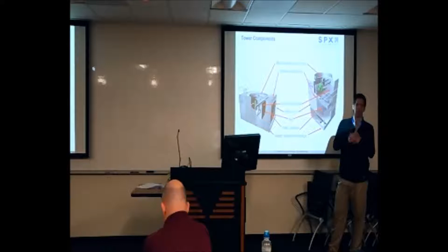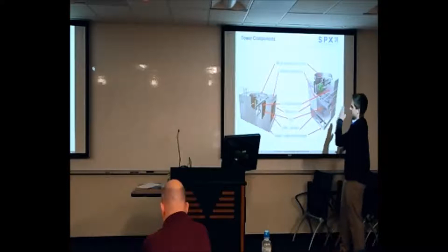We also have, integral to the fill, louvers, which are the first point of contact for the air. The purpose of the louvers is to keep the water inside the tower. Without louvers, the water would just fall out of the fill. It may fall in the basin, or it may fall out of the tower completely. So the louvers, which are connected to the fill, are angled such that water that falls on them will be directed back inside the tower.